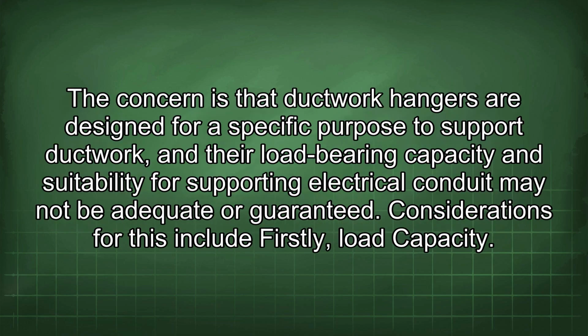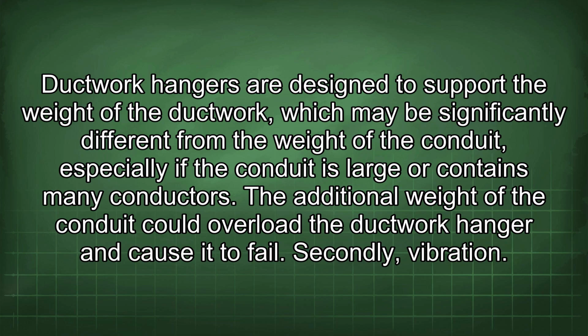The concern is that ductwork hangers are designed for a specific purpose, to support ductwork, and their load-bearing capacity and suitability for supporting electrical conduit may not be adequate or guaranteed. Considerations for this include, firstly, load capacity. Ductwork hangers are designed to support the weight of the ductwork, which may be significantly different from the weight of the conduit, especially if the conduit is large or contains many conductors. The additional weight of the conduit could overload the ductwork hanger and cause it to fail.